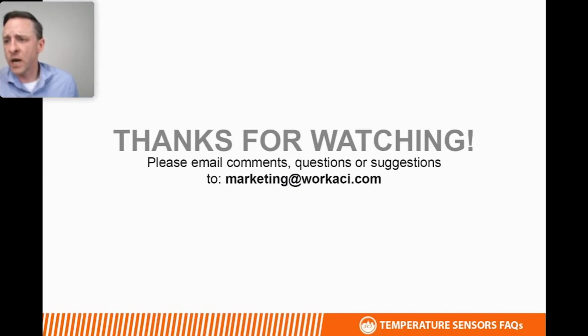A question came in on the chat from Kyle. Thanks, Kyle. He says, is there a maximum length a sensor can be run before it starts losing accuracy? Yes and no. One of the advantages of thermistors, and I said I wasn't going to go into the advantages and disadvantages, is that they typically experience less voltage drop over longer lead runs than RTDs do. If you have an application where you need to run wire over a longer distance, we'd recommend a thermistor.